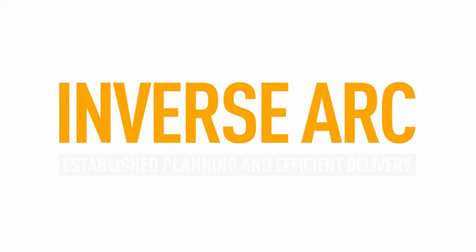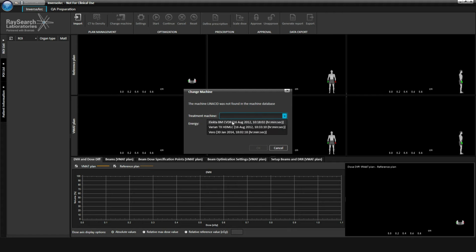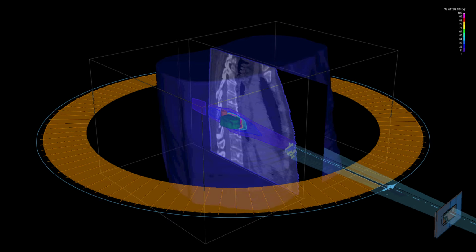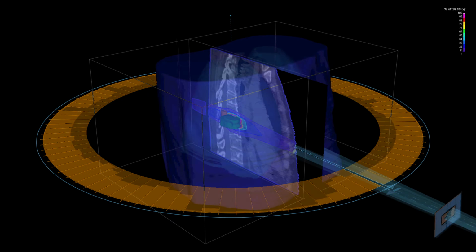Inverse arc reproduces the dose characteristics of any given treatment plan with a volumetric modulated arc treatment technique. Depending on linac capabilities, the software optimizes the plan either with a fixed or modulated dose. The fixed dose option optimizes leaf position while ensuring that every segment receives the same dose, resulting in a constant dose rate and constant gantry speed during delivery.